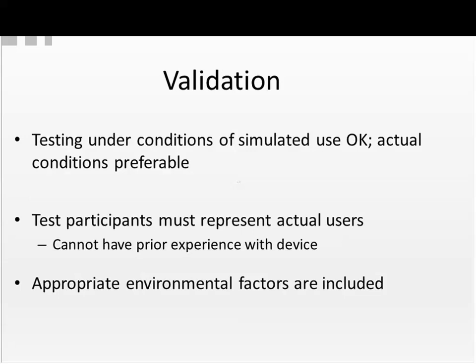Now, the testing under conditions of simulated use is okay, but actual conditions are preferable if it can be accomplished, usually not. The test participants must represent actual users, and they cannot have prior experience with the device. This excludes company employees, even if they fit the profile of a participant.